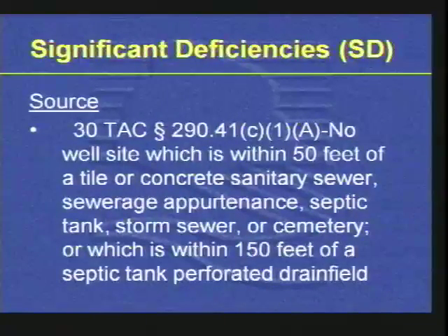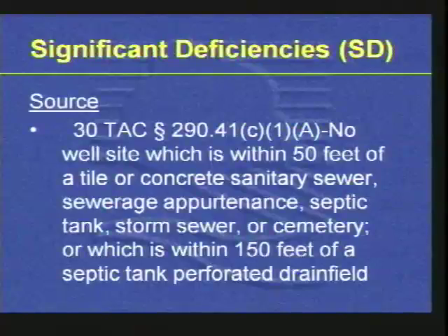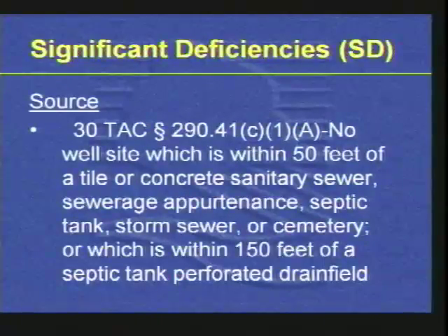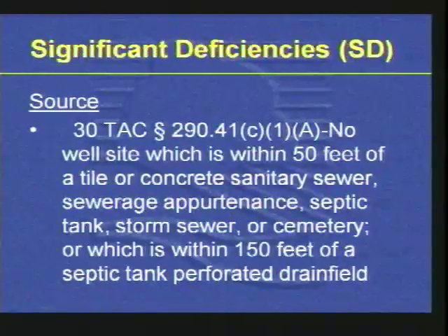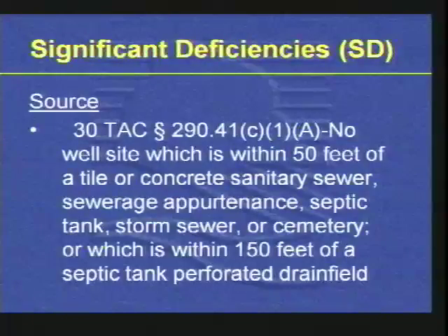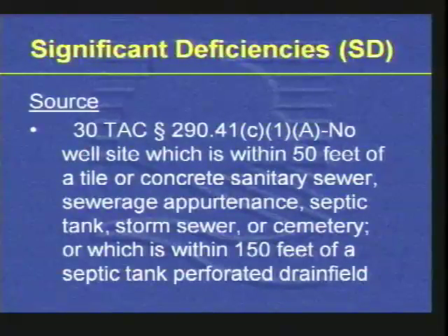Let's go through that list. The first element is source. Rule citation 290.41 C1A — no well site which is within 50 feet of a tile or concrete sanitary sewer, sewage appurtenance, septic tank, storm sewer, or cemetery, or which is within 150 feet of a septic tank perforated drain field.